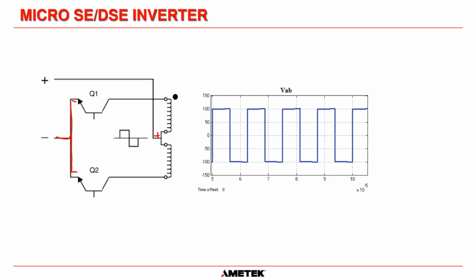So what we're doing is, depending on which IGBT we switch on, depends on which side of the transformer we connect the negative of the battery to. And I'll explain this in just a moment. So first of all, we're going to turn on Q1. So once again, remember, power to the center tap of the transformer, it's always going to be positive there. But now, because we have turned Q1 on, remember, when we turn it on, it just becomes a direct short between the collector and the emitter. So negative gets connected to this side of the transformer.